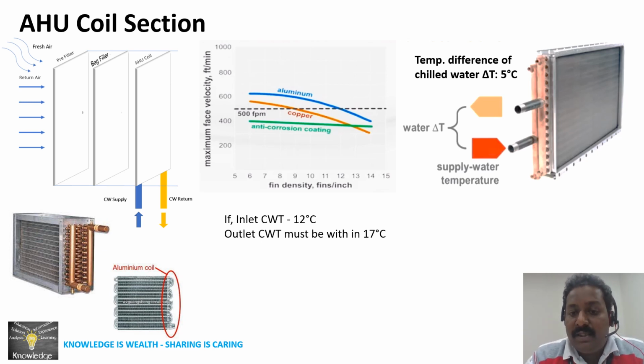So that integration, if it is not working properly and there's no occupancy or less occupancy, it is still running at full speed. With the actuator, you will then get a delta T of less than 1 or 2. So less than 1 or 2, a low delta, is also a problem. You need to always monitor low delta and check the communication part of the AHU and set it right. Then you can get a delta between 3, 4 and 5, which will be very good.